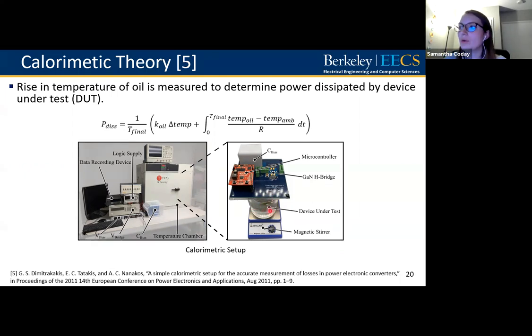Here's our beaker of oil, here's our device under test. It sits on top of a magnetic stirrer, and we do this so that we have equal temperature throughout the oil. And then, like I mentioned on the last slide, we have our H-bridge mounted directly on top of the device under test. You can't see it here, but below this we use large pieces of copper to go to our device under test. And then we have our microcontroller here as well. This again is mounted directly on the beaker so that we're as close to our device under test as possible. All of this system goes inside this temperature chamber here.